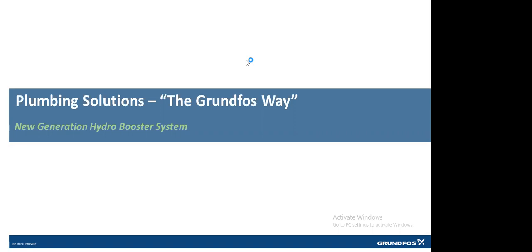Got it, sir. Sir, as discussed in head calculations, total head is nothing but static head plus dynamic head. So our static head is 55 meters, that is fixed. And also we need to take into account dynamic head, and then we need to calculate the total head. And in this case, what might be happening? The pump is operating at 60 meters head only. So the dynamic frictional losses would be more in the pipeline, and that may be the possible reason for not getting the flow at the topmost floors. So in that case, we may need to install the booster pump in between so that we can pass the flow to the topmost floor.